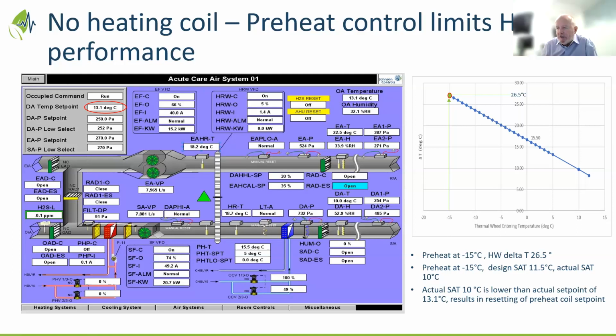So Amadou, sorry to keep interrupting, but you're just using this control diagram to explain the problem: with the absence of a reheat coil, if you haven't got the supply temperature you're looking for, then you have to pump it in preheat, and that kills the wheel. Exactly. That's not what's happening here, right? Because it's 13.1 degrees Celsius outside. No, this is just used to explain the background. So this is just illustrating the system. Exactly. Yeah, that's not what's happening.